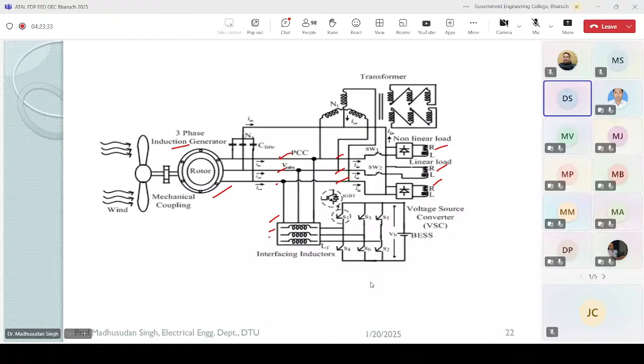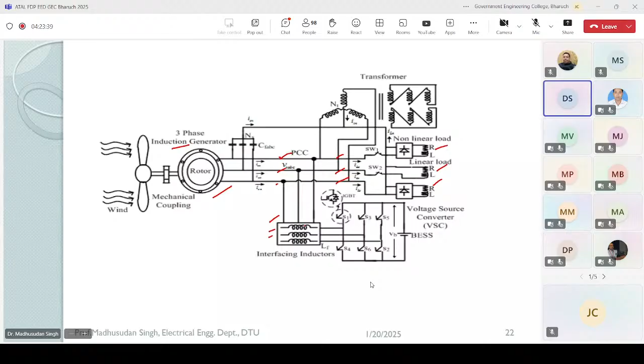So here also you have 3 single phase nonlinear loads demonstrated, so that if this generator faces a worst case loading of 3 phase load, maybe with single phasing and all, we see how we are able to maintain voltage at PCC and also the frequency, and we ensure the quality of power supply here at the load terminal. So you have a 3-phase VSC here with a battery energy storage, a DC link, and an interface inductor which is required to connect this VSC to the PCC. So the value of this interfacing inductor is also important when you connect any VSC at the PCC.